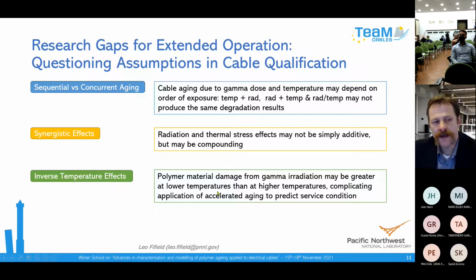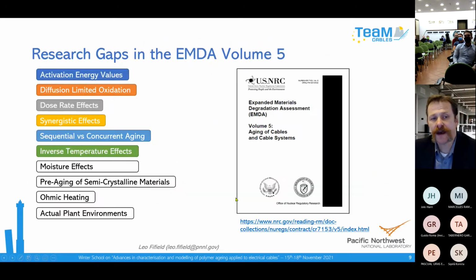And the final one is the inverse temperature effect. It's been observed in the laboratory in some cases that gamma radiation is more destructive to the polymers at lower temperatures, counterintuitively, than it is at higher temperatures. Normally in long-term plant operation, the temperatures would be relatively mild, and if cable polymers are exposed to gamma radiation under mild conditions, the concern is they might age more rapidly than when you apply radiation and high temperature at the same time in the laboratory. So those are some of the knowledge gaps that the cable aging program has been addressing.